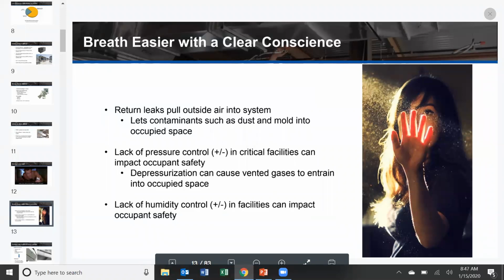Over or under pressurization from duct leaks and imbalanced duct systems can cause spillage of combustion products, for example from furnaces, water heaters, and fireplaces, into the building. It can also negatively impact critical rooms such as surgery suites that we all know must remain in a slight positive pressure state to keep any potentially harmful bacteria or debris from coming into the surgery suite. Lack of humidity control can also impact occupant safety.